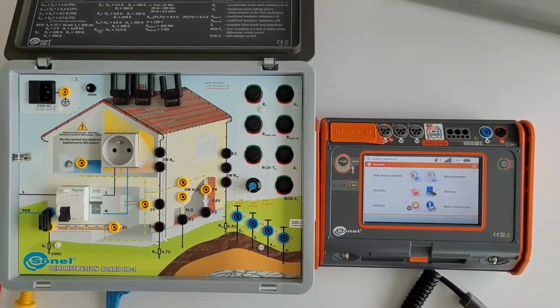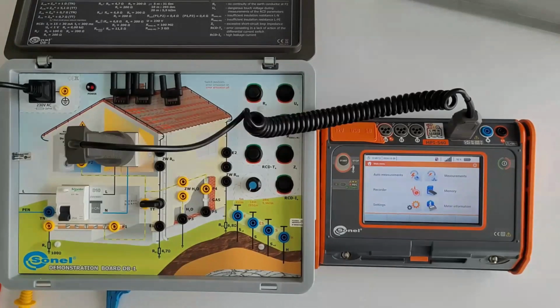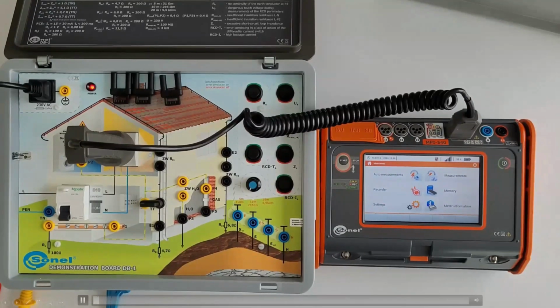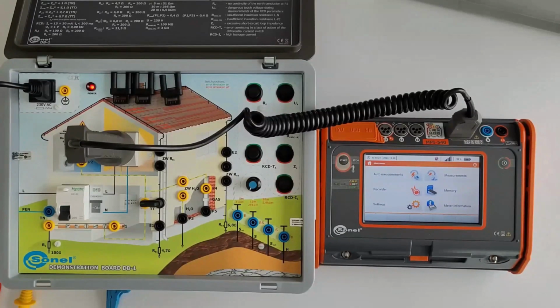So next we have RCD parameter testing. In PV systems, sometimes we have an RCD, sometimes we don't, but I want to show you. We measure the trip current and trip time for the rated current. The standards don't require us to measure all the parameters of the RCD. We need only check the trip current and trip time for the rated current.